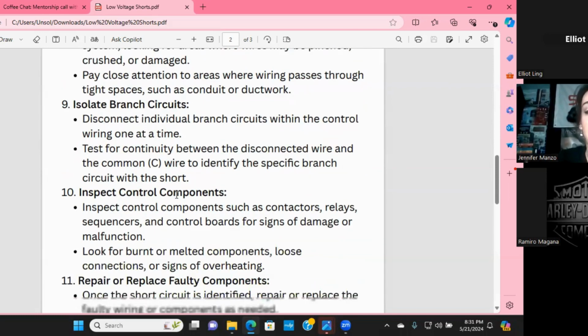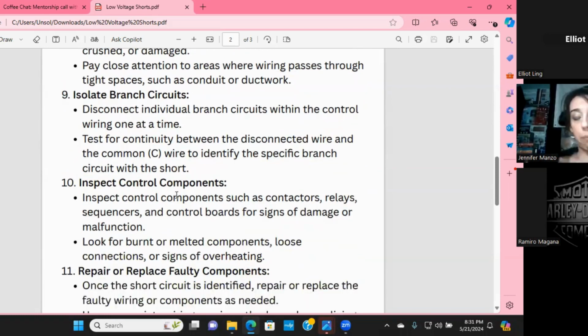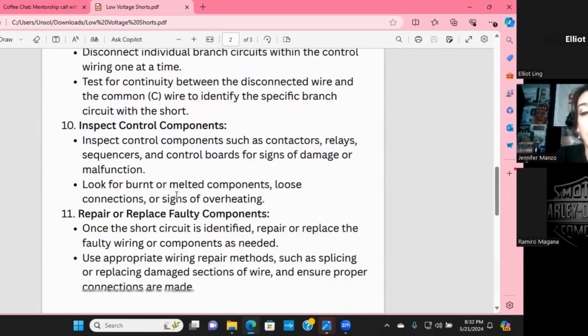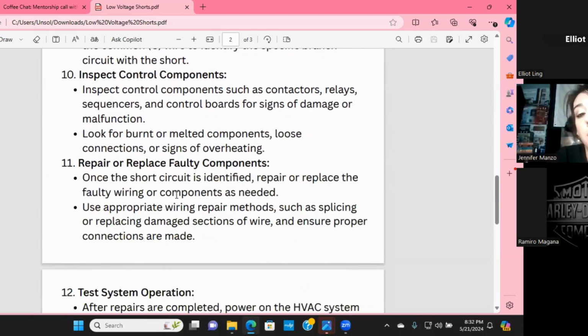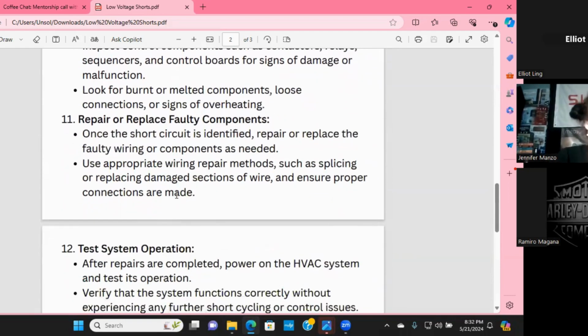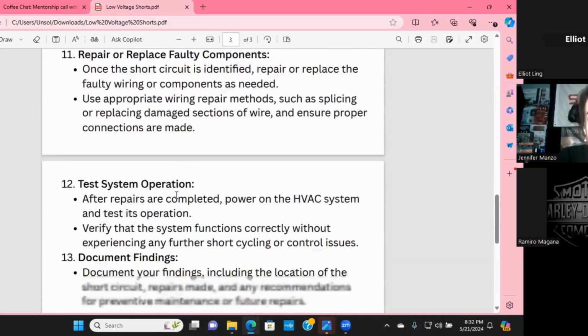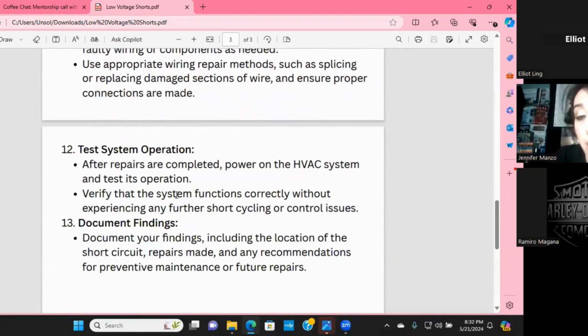You can isolate your branch circuits if you need to. If you get to that point in your troubleshooting, you can inspect the control components. A lot of the time, a 24 volt short will come from some sort of control because that's on the 24 volt side of the system. And then you just replace or repair faulty components. When it comes to electrical, I don't recommend repairing them. I always replace. It's up to you.